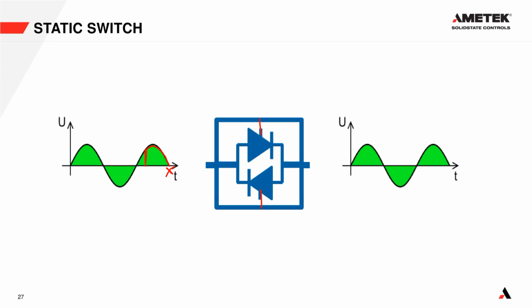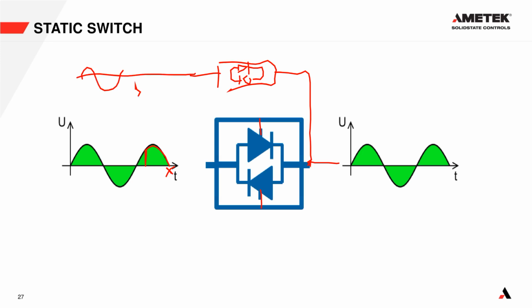And that's actually a very good thing when it comes to a static switch. Because in theory, what you have is your inverter static switch and your bypass static switch, connected together like this, and they go out. We have a waveform that is in synchronization, so this is the bypass and this is the inverter. What we can do is, when you press the bypass to load push button on a UPS, let's say we pushed it at this point, this portion of the inverter carries on conducting. And then this portion of the bypass, if you follow it down, will conduct as well. So they'll conduct in parallel.